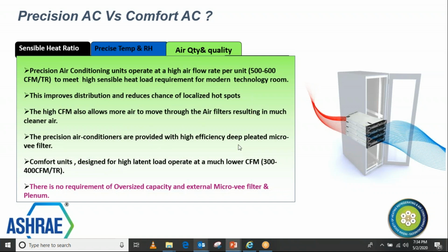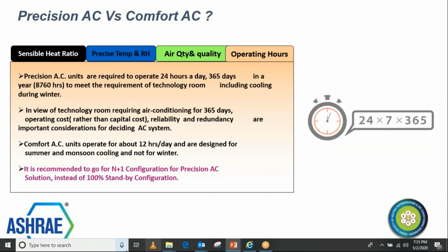Which means, the same way we did for sensible cooling, when you have to meet the 10 TR requirement of sensible cooling, you have to install a much higher capacity of comfort system. Here also, when you have to match the airflow per TR, or the airflow requirement for high sensible cooling, you have to install more capacity of comfort air conditioning system. Obviously, when you install more, it is going to consume more. It's understood there. So these are the important points to note here.